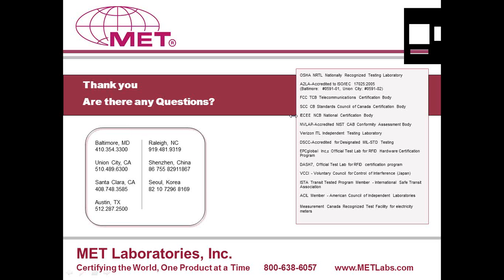There's an aside there: is test number 20, the temporary overload, required for meters that use CTs? The answer to that is no. Test number 20 for that temporary overload, where you get 7,000 amps peak running through the product in a fault condition and 10 or 12,000 amps RMS, we're simulating that in the lab. But because the CT is external to the product, we're really running that test only on self-contained meter products. So if you have a product with external CTs, we're going to call that not applicable for a typical test program.